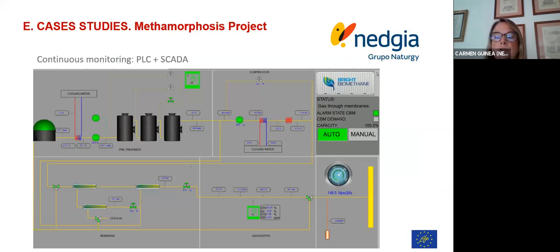The upgrading plant is monitored continuously by means of this PLC. In the control scheme the process can be seen starting from the digester on the left, followed by the heat exchanger, the blower, the filters, and the compressors. In order to monitor the biogas and biomethane, the plant also includes 2 multi-analyzers. These analyzers take samples from different points of the process. The lower the methane concentration is in the biogas, the higher the required discharge pressure. Finally, the biomethane coming from the membranes with over 95% methane is sent to the refueling station. In case the biomethane does not comply with the quality, it will go back to the digester. We don't release any methane to the atmosphere.